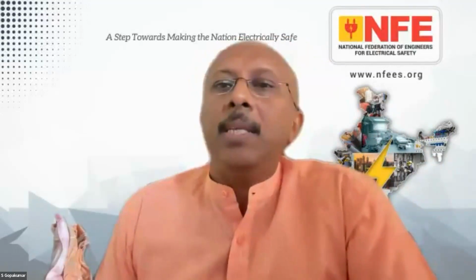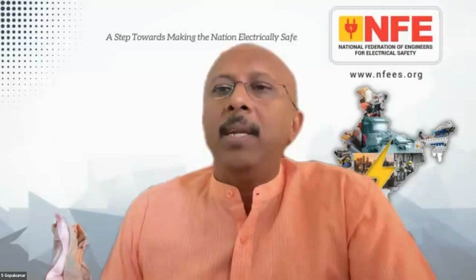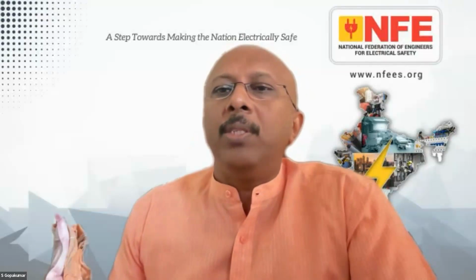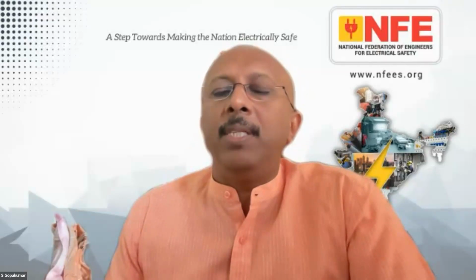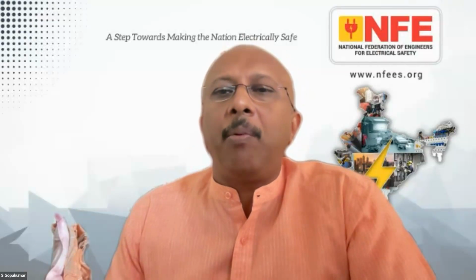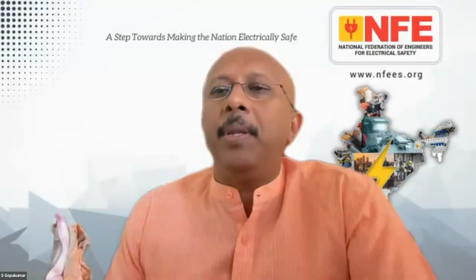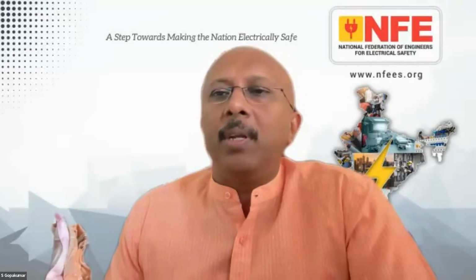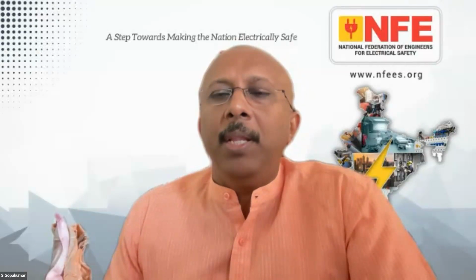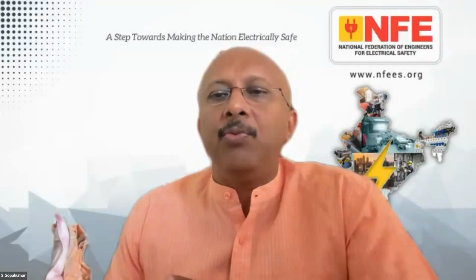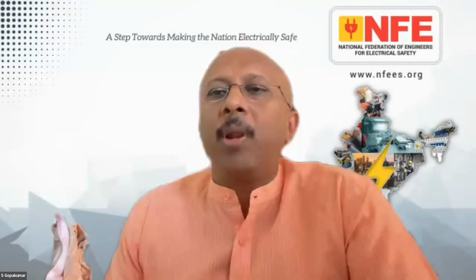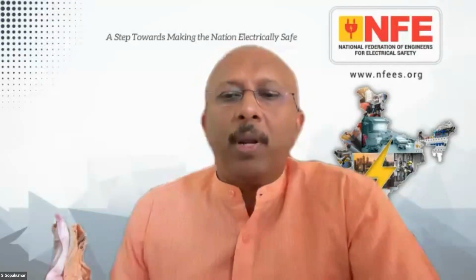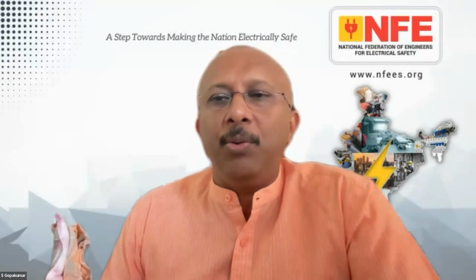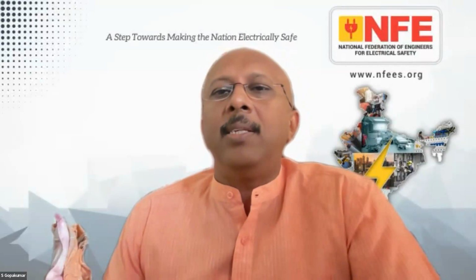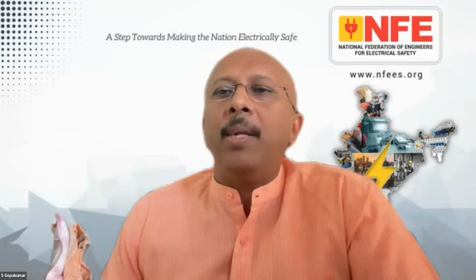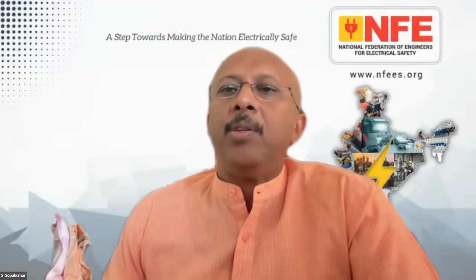So Mr. Chetan is asking, what is the solution for existing TT system? How is protection done in a lift? Mr. Chetan, very simple. You have to install an RCD, probably type B 300 milliampere, for fault protection. It doesn't mean that you don't need an MCB. Your MCB is for line to neutral or overcurrent protection, which must be there, and this RCD is an additional protection for additional fault protection.